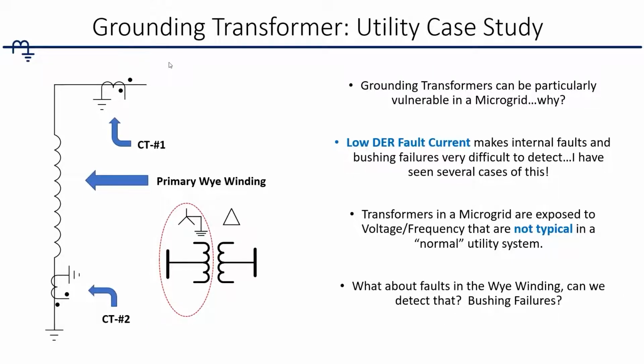So like we said, grounding transformers are particularly vulnerable. And why is that? What I found is, not a big surprise here, but we all kind of know implicitly that inverters supply very little fault current availability compared to rotating machines. So it makes internal faults within transformers very difficult to detect.